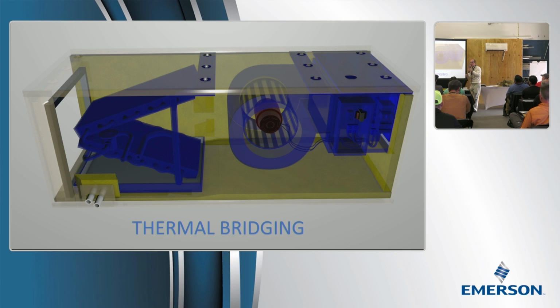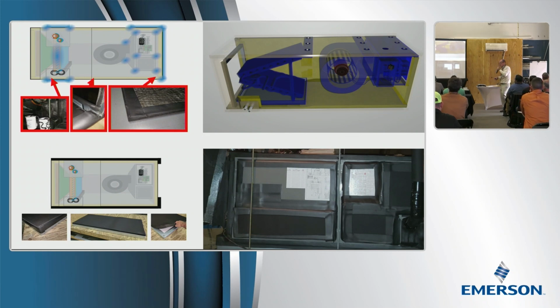So that's the thermal bridging. You know before you even go where they're going to sweat. They're going to sweat right there where all that cold metal is squeezing this 3/4 inch insulation down to 1/4. And they've recessed the screws, so everything's pinched together and you don't have the intended R-values. If you look in the brochure that comes with the air handler, it'll say it's got R6 insulation in it. Well, it's mostly R6. What about where you pinched it under the drain pan? What about where you pinched it right here? So we know where it's going to sweat. It's predictable just by looking at them. We have some success re-insulating them using technology that we discovered drinking beer.